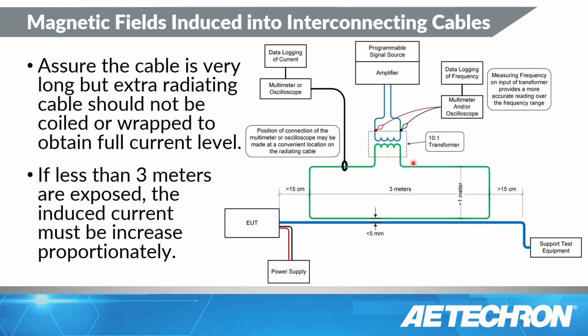The reason why, and I did this myself, I had that wire coiled up on the bench, did the calibration, found I needed quite a bit of power on this side to push current through that inductor. And when I went to do the final test, I had the wire straight. Well, that's much lower inductance, as it turns out, than a coil of wire. And as a result, I was trying to push the same amount of current, and I was way over testing. I just about melted the insulation off that wire. So don't coil wires either in calibration or during the test.